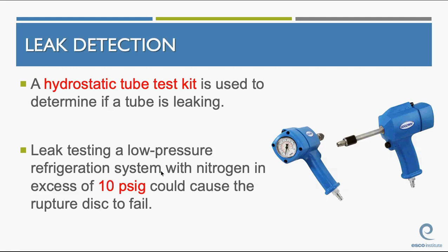A hydrostatic test kit is used to determine if a tube is leaking. What is a hydrostatic test kit? Okay, if you look here on this picture right here, I have a spot for a connection, right? So I connect my nitrogen right there. I put this into the chiller tube I'm worried about after it's recovered and isolated. I can pressurize that tube and make sure the pressures don't drop.